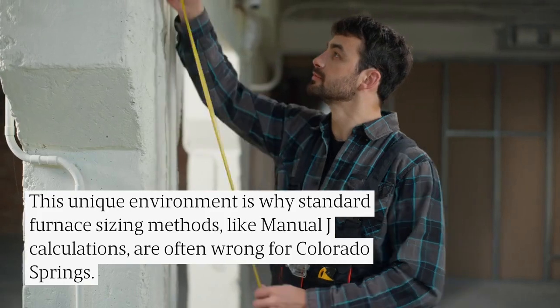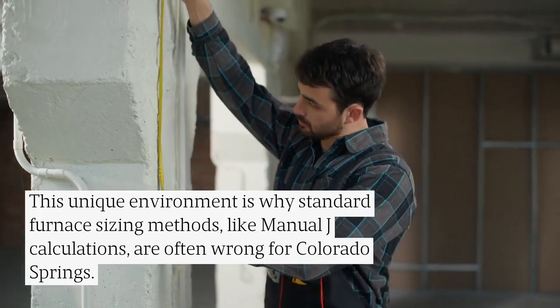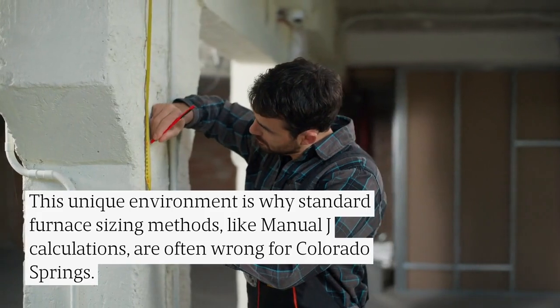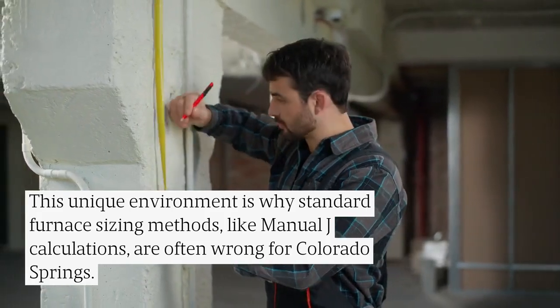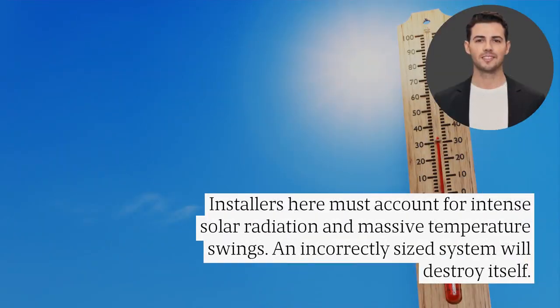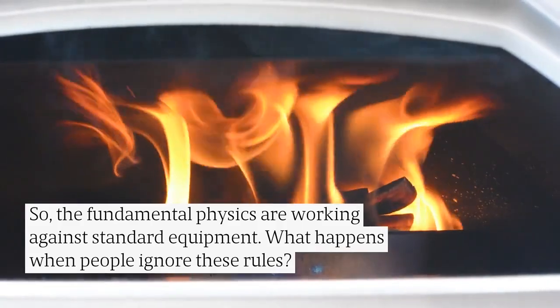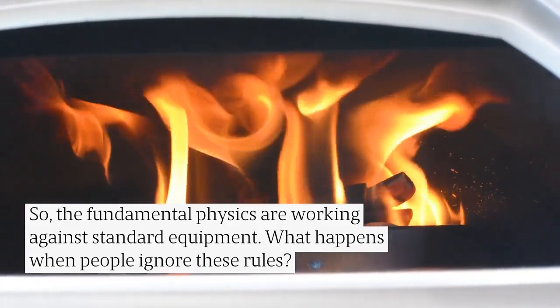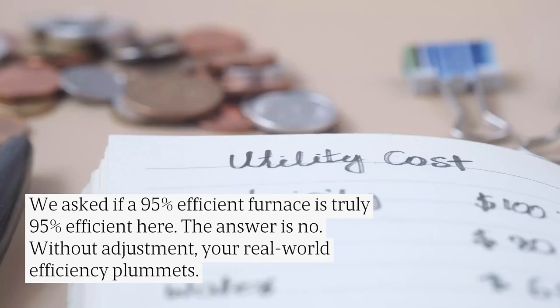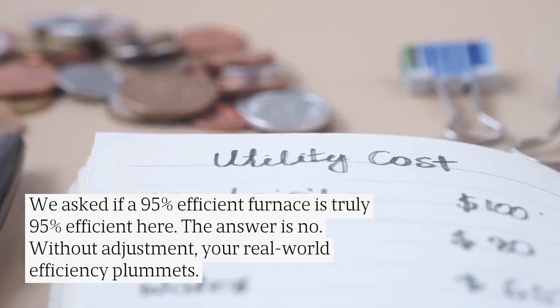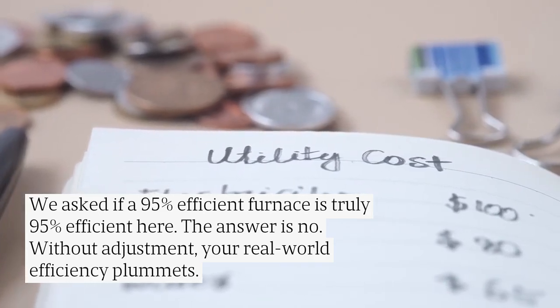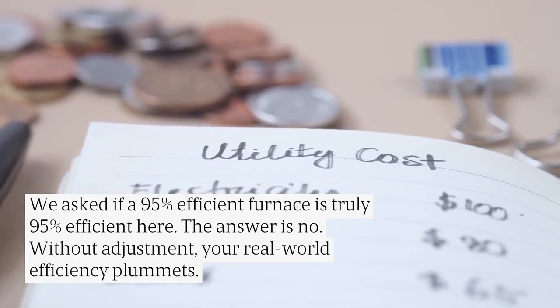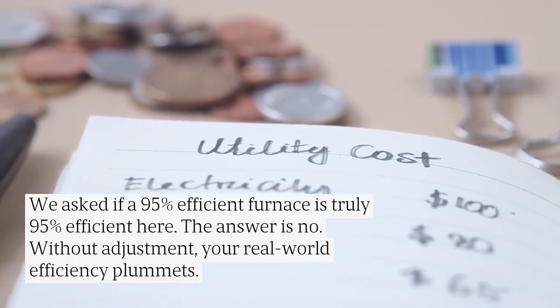This unique environment is why standard furnace sizing methods, like Manual J calculations, are often wrong for Colorado Springs. Installers here must account for intense solar radiation and massive temperature swings. An incorrectly sized system will destroy itself. So, the fundamental physics are working against standard equipment. What happens when people ignore these rules? We asked if a 95% efficient furnace is truly 95% efficient here. The answer is no. Without adjustment, your real-world efficiency plummets.